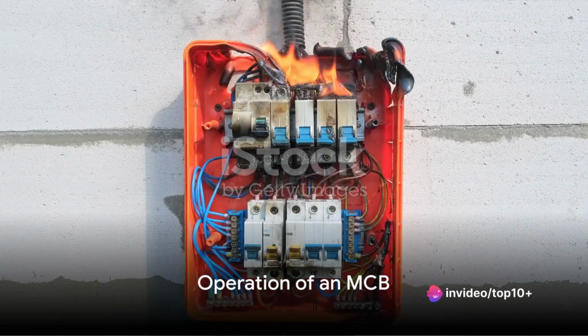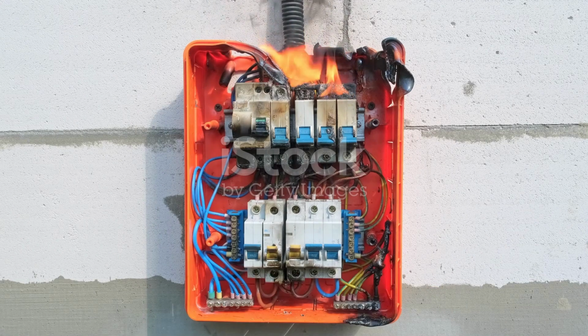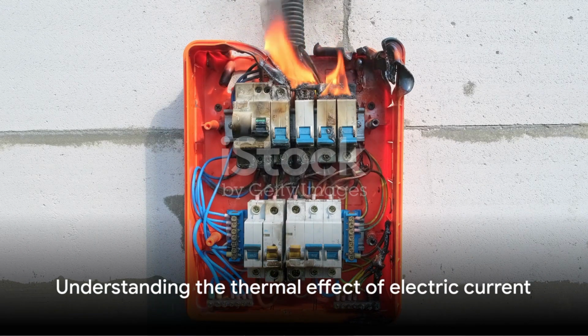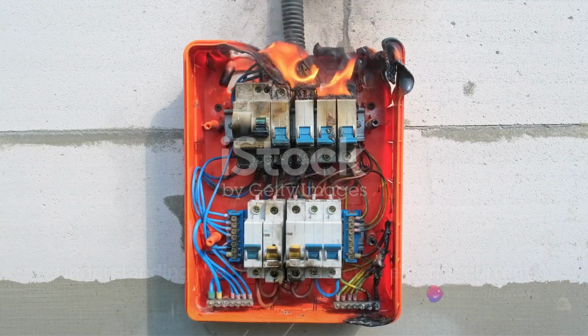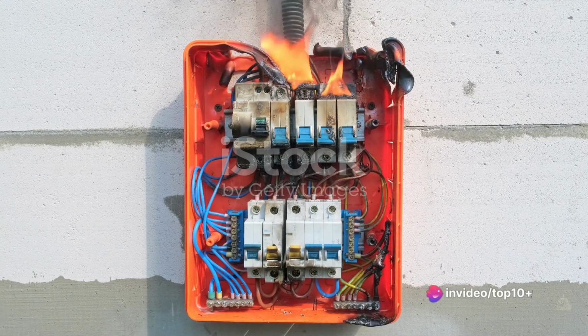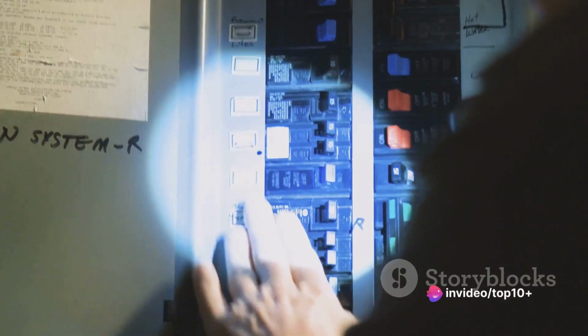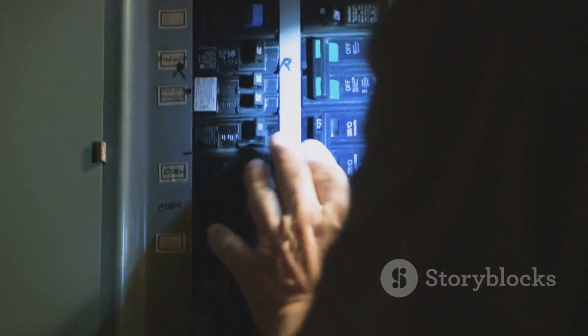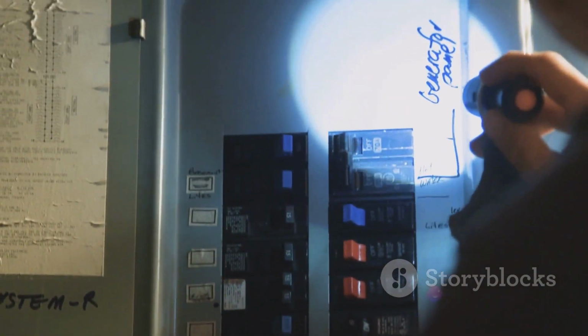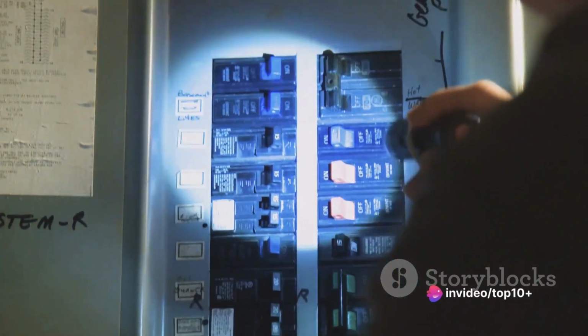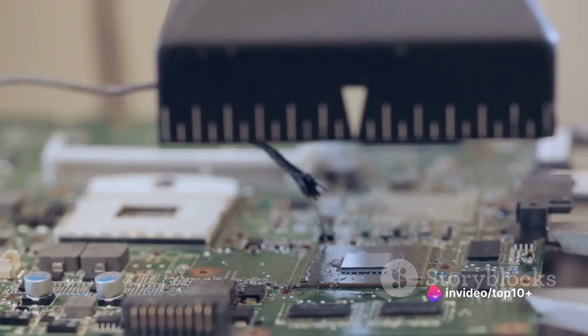The operation of an MCB revolves around two fundamental principles of electricity. Firstly, we have the thermal effect of electric current. It's a simple yet crucial concept. As electrical current passes through the MCB, it generates heat due to the resistance in the path. Now, in normal conditions, this heat is harmless. But when the current exceeds the safety limit, the heat generated also spikes. This excessive heat is used to trigger a mechanism in the MCB that disconnects the circuit, thereby protecting your appliances from damage. It's like a guardian, constantly watching over the electric current's thermal effect.